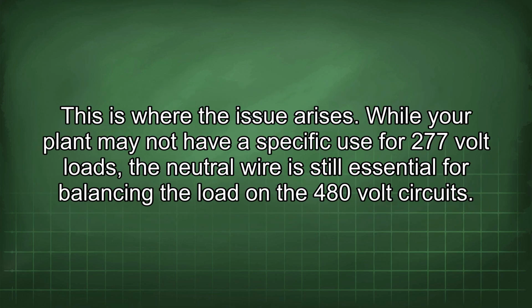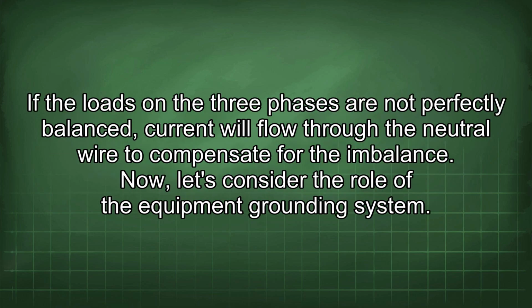This is where the issue arises. While your plant may not have a specific use for 277 volt loads, the neutral wire is still essential for balancing the load on the 480 volt circuit. If the loads on the three phases are not perfectly balanced, current will flow through the neutral wire to compensate for the imbalance. Now, let's consider the role of the equipment grounding system.